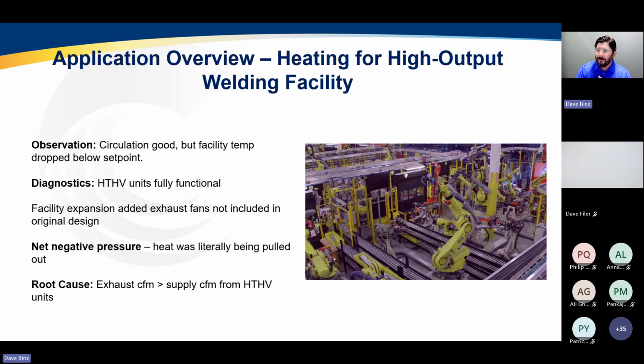Well, as design professionals, we want to stop and look at the whole building, look at the operations, and realize you actually have a negative pressure problem. You've got a ventilation problem. You don't have adequate ventilation for all this process you've added. And now this facility happened to do it all at once. In most buildings, you see them added one at a time: one exhaust fan here, one exhaust fan here, one exhaust fan here. And slowly over time, the temperature becomes colder and colder, and the negative pressure gets worse and worse. But this was all at once.